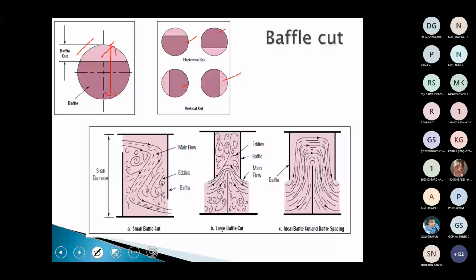Coming to the importance of baffle cut: if the baffle cut is made small, for example 10% or 15%, what happens? You can see this is the baffle cut, a very small cut. The fluid enters here and flows like this, so there may be a lot of eddies, and these are called dead zones. So the heat transfer efficiency will drastically go down.